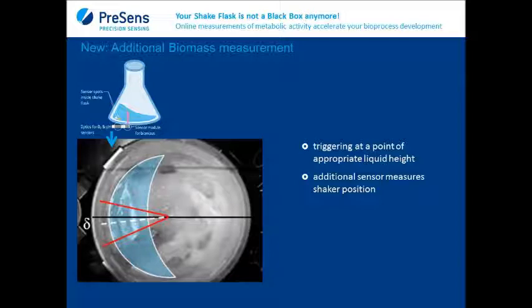It's a fluorescent technology, so the way it works is you shine a pulse of excitation light onto the sensor spot, and the sensor spot will react by emitting fluorescent light. This fluorescence is dependent on the concentration of the analyte. So a change in pH or a change in the oxygen concentration will change either the fluorescence intensity or the fluorescence lifetime. And that's actually what we're detecting. This is a photograph of an actual reading. A reading itself will take about 200 milliseconds. So you can sample the readings down to 1 reading per second, pH, oxygen, and biomass.